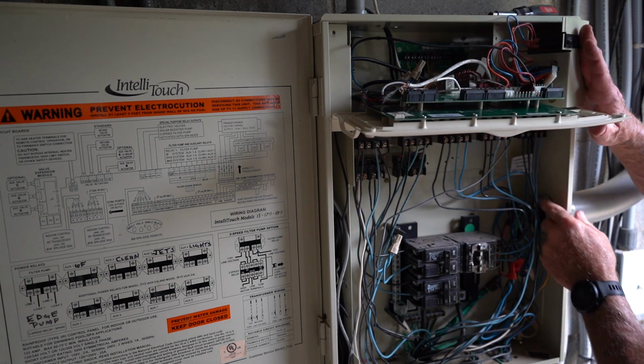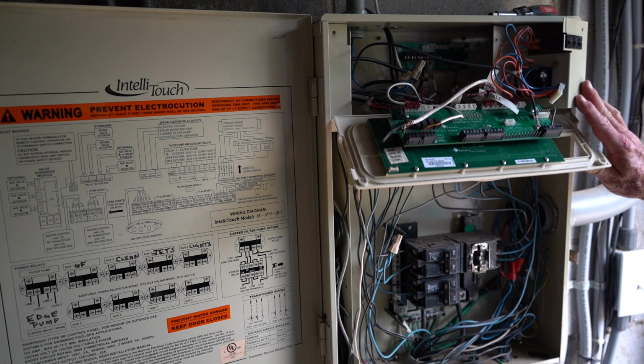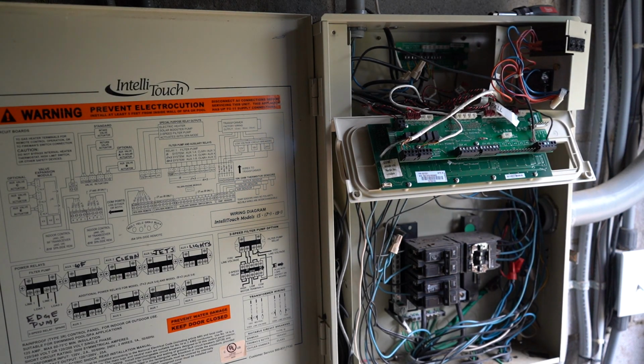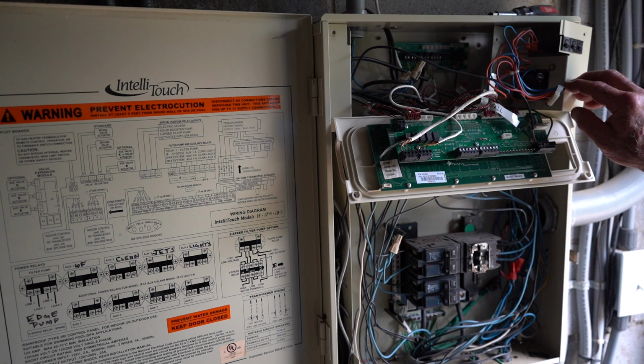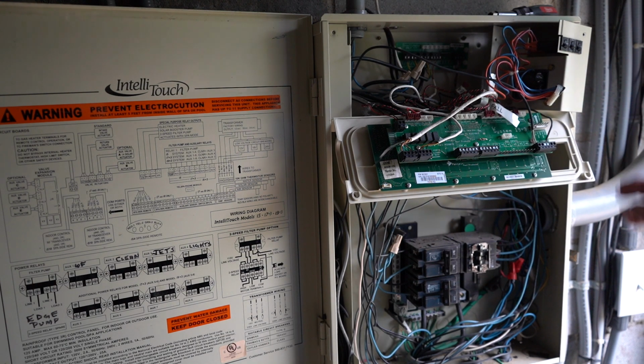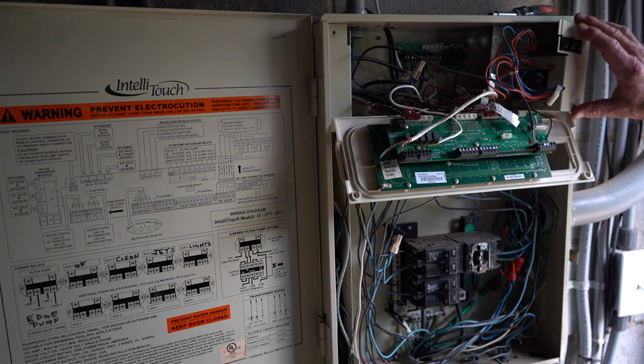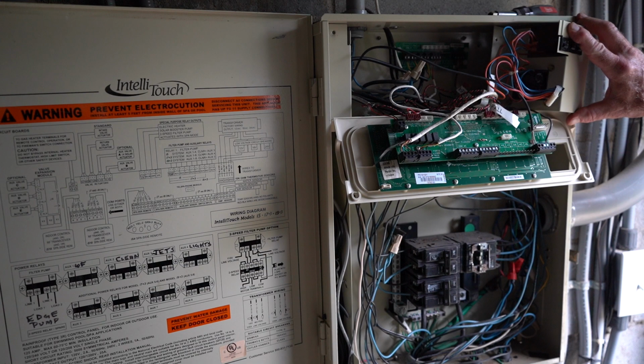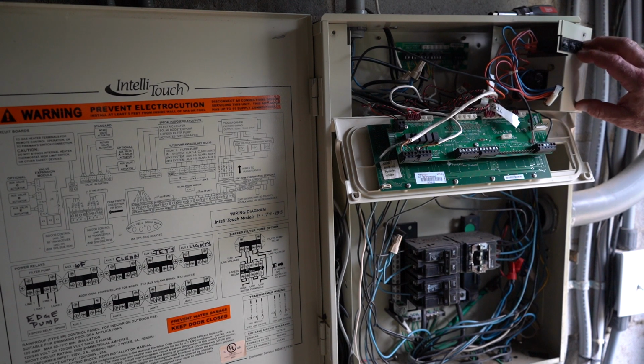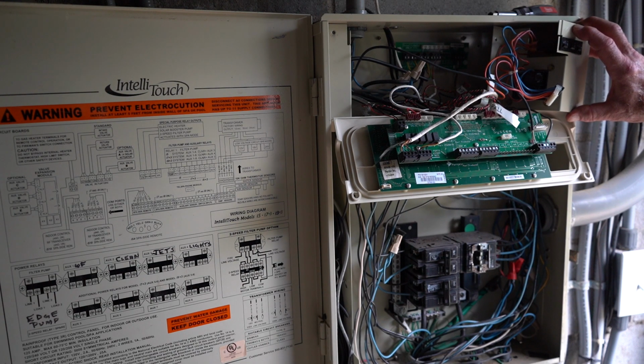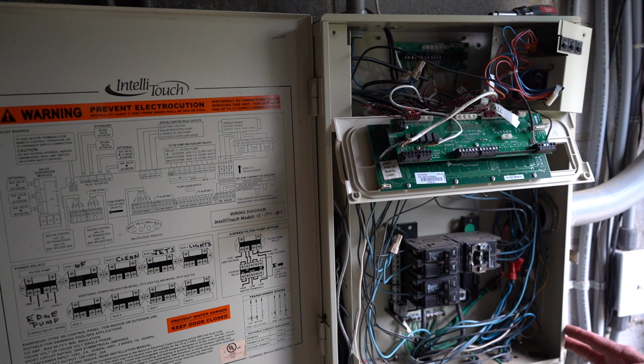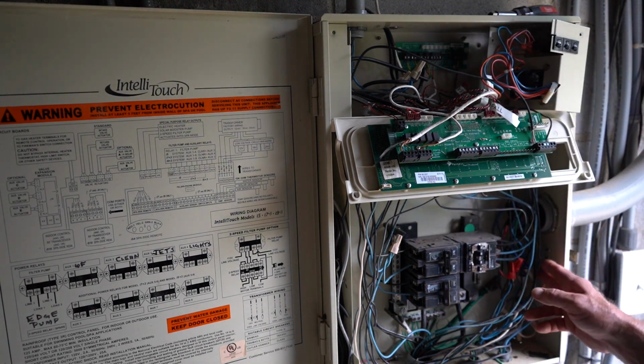This is wired for 240 volts, and that's a problem with the Jandy system. Pentair's transformer allows you to wire it for either 120 or 240 with a simple change, but the Jandy transformer will only work on 120 volts. Be very careful, because all of them ship from Pentair wired for 240 volts, and you'd have to convert it to 120 if you only have a single circuit breaker. You can see the wiring coming down here.